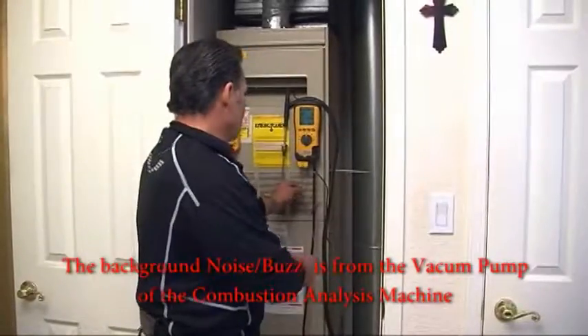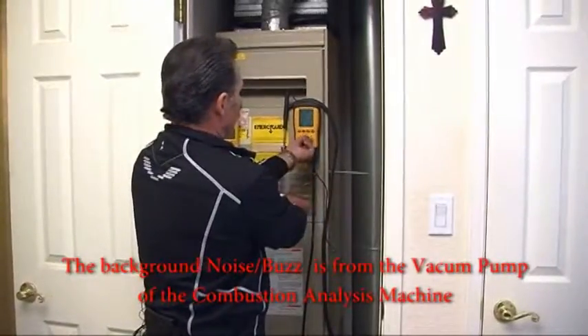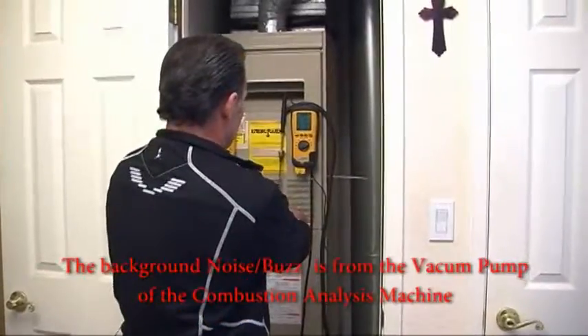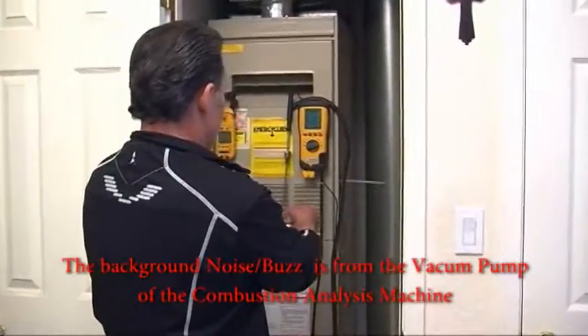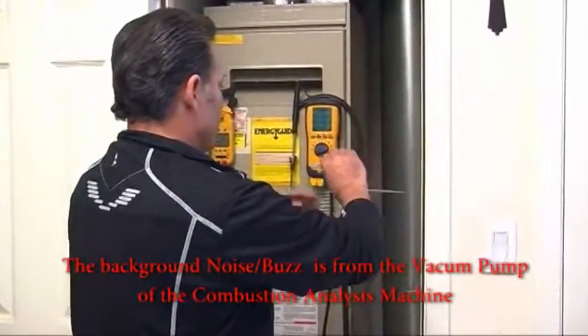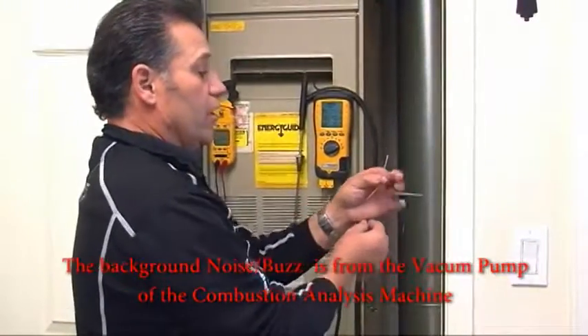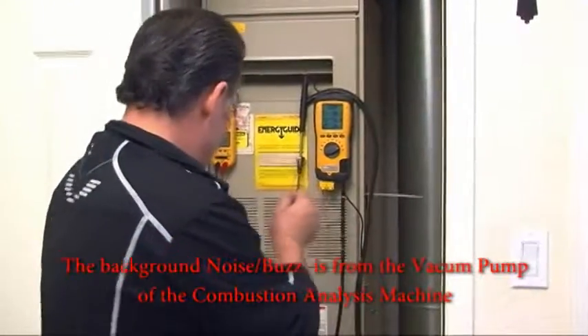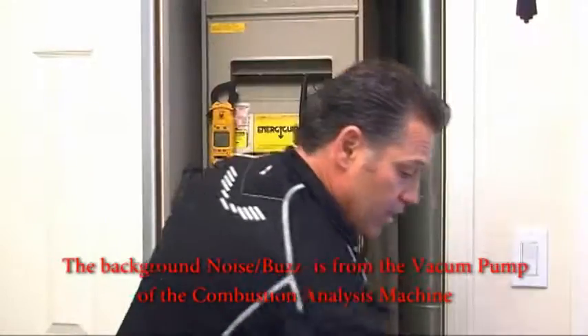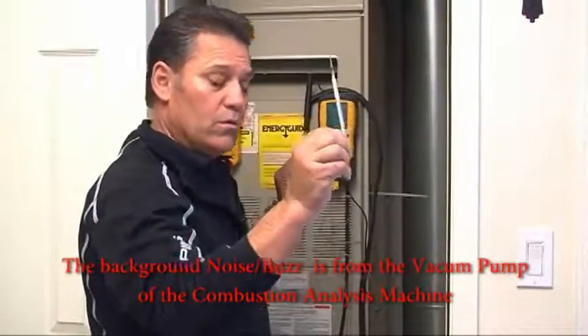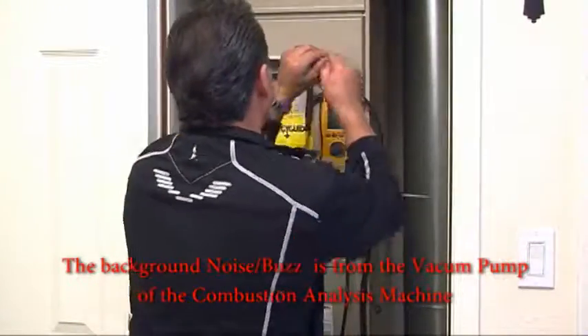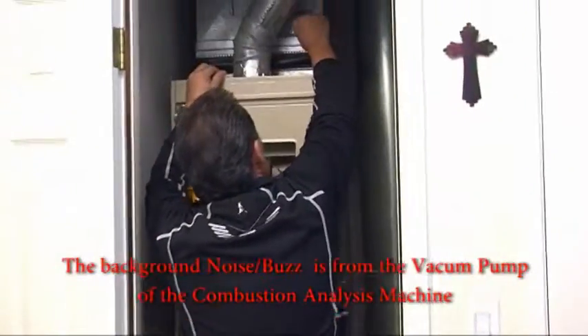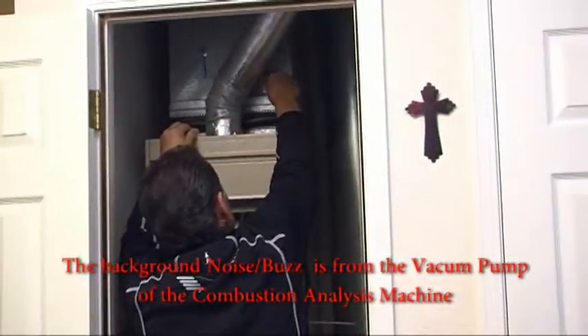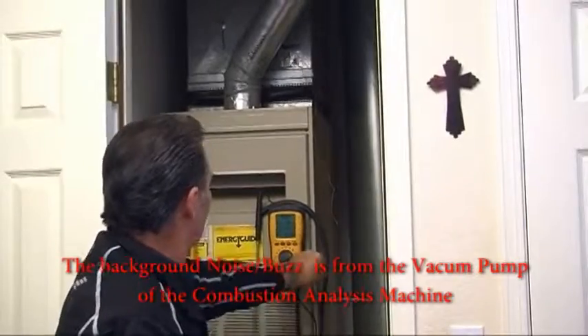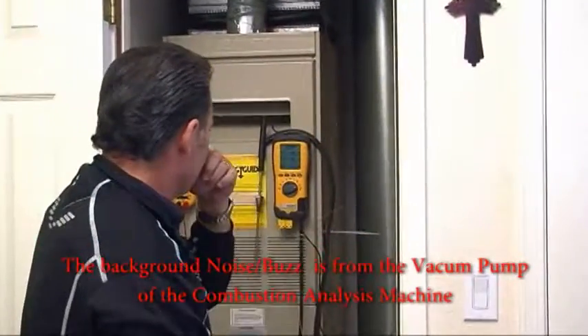So I've hooked up my thermistors. I will turn my machine to temperature. It'll give me a T1 and a T2 and a delta T. So here's my thermistor for my supply. My return's already in. I've made my hole with this little poker, and I will put this up into the supply. The furnace has been running for a few minutes, so it's at steady state.